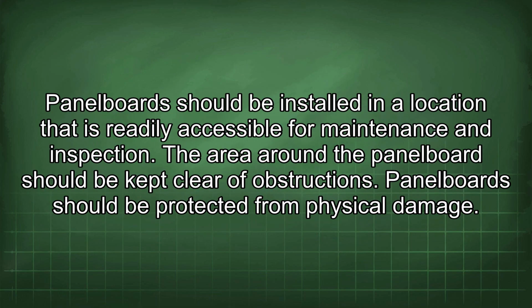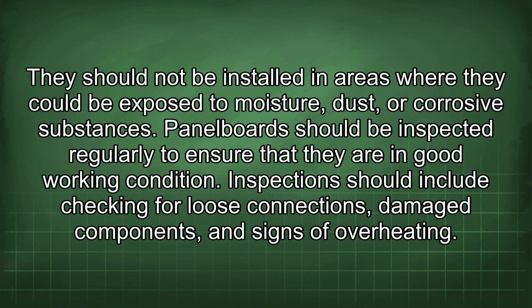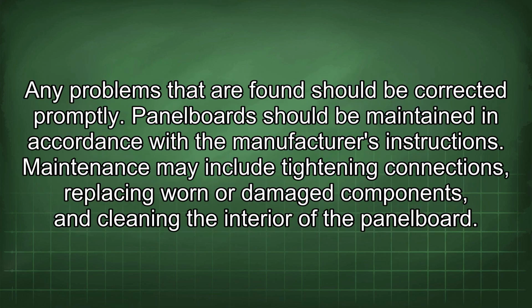Panelboards should be installed in a location that is readily accessible for maintenance and inspection. The area around the panelboard should be kept clear of obstructions. Panelboards should be protected from physical damage. They should not be installed in areas where they could be exposed to moisture, dust, or corrosive substances. Panelboards should be inspected regularly to ensure that they are in good working condition. Inspections should include checking for loose connections, damaged components, and signs of overheating. Any problems that are found should be corrected promptly.